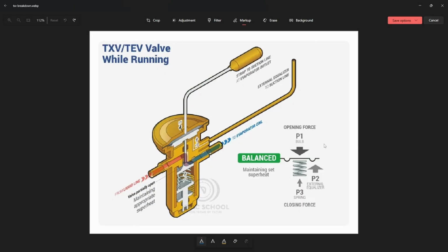With an EEV, or an electronic expansion valve, they react much faster, which is why we have to use them in some circumstances. It's also why they work best or better in some applications than a slow moving TXV would. Because remember, superheat is what we check to make sure our compressor is safe. Superheat is a measurement of the amount of degrees above boiling our refrigerant is as it leaves the evaporator coil. It's how we make sure we have 100% vapor or gas refrigerant going out of the suction line to our compressor. So it's important that we have a valve that can keep up with the compressor's pump rate or compressor's capacity and respond quick enough to protect our compressor at all times, regardless of how fast our compressor may be pumping, or slow in the terms of an inverter driven system or a modulating system.